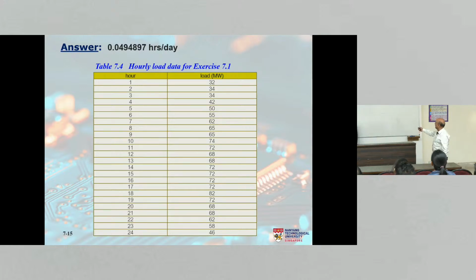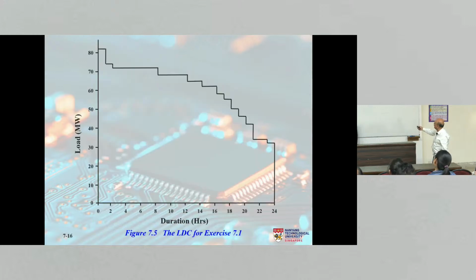So 82 is the highest load and 32 is the lowest. So here it is, 82, you're right. 82 all the way down to something like 32 or 34, whatever it is. So hourly, right? It's changing hourly, correct? So it's not like a straight line. You can approximate it using your least squares error algorithm and things like that by a straight line if you want. But it's 24 hours. It's not 8760 hours. So it's very doable by hand calculations.